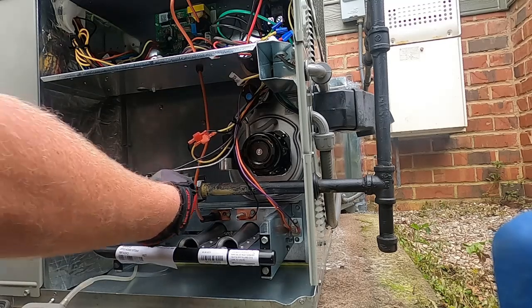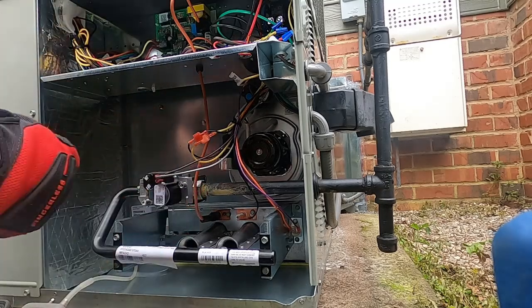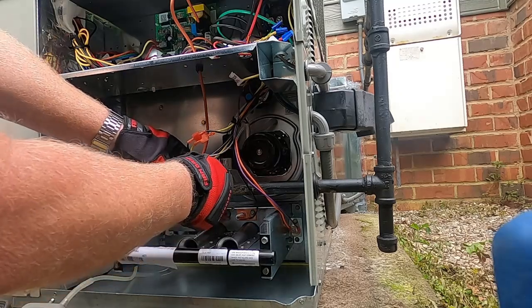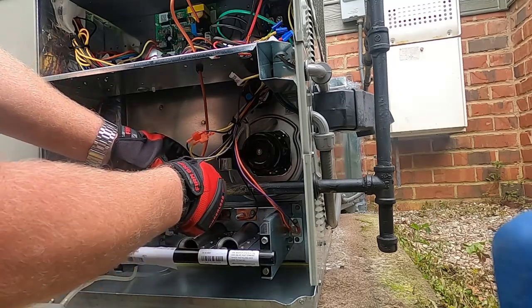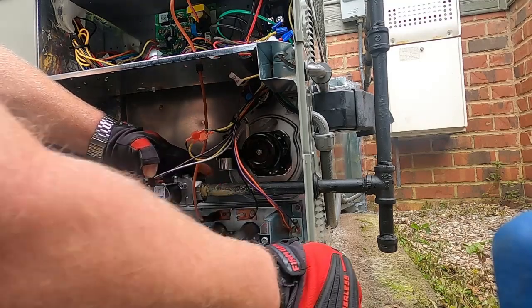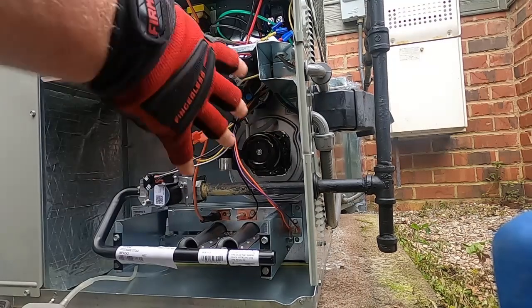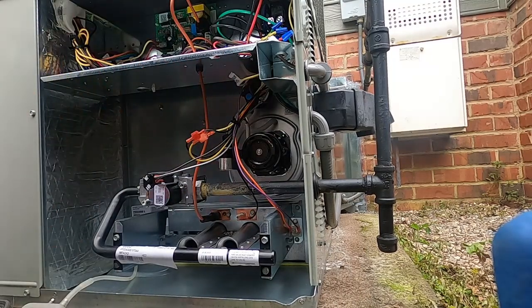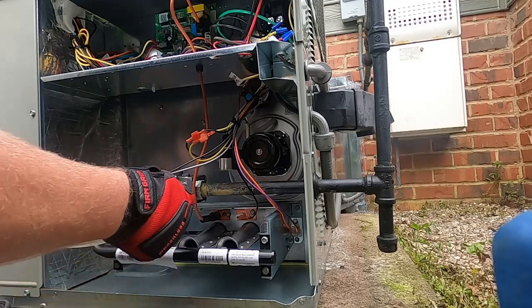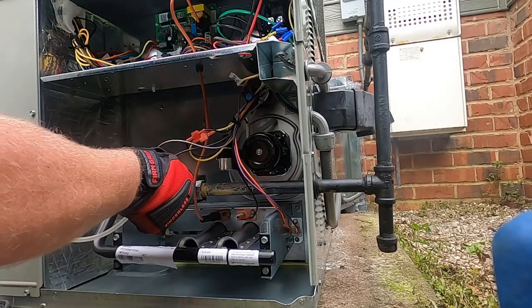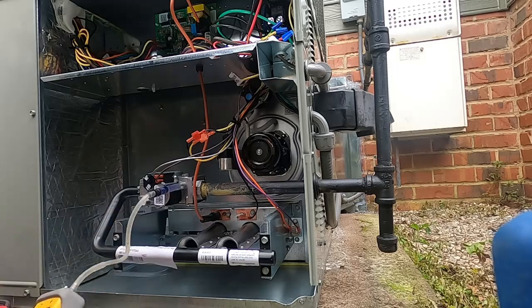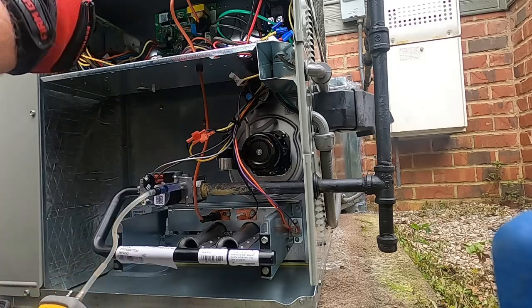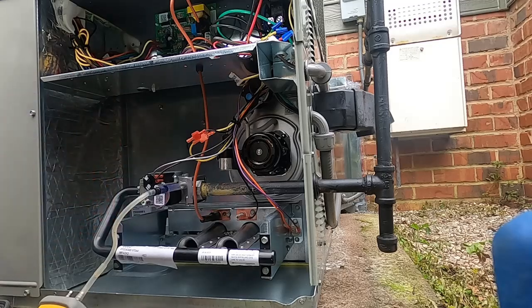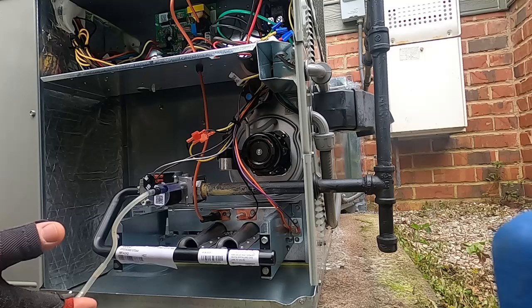So when I'm setting gas pressures, I just use a good old-fashioned digital manometer, and I strictly use those if I'm doing a system performance evaluation. Throw them in there on the plenums and check my statics, all that stuff. In that particular scenario, I want to use the Measure Quick app, where I do a total system performance evaluation. I'm not doing that here. And my third air probe that I would have outside getting wet bulb and all that mess is actually at home. So go figure. But anyway, this is something kind of simple, but we have to do it.